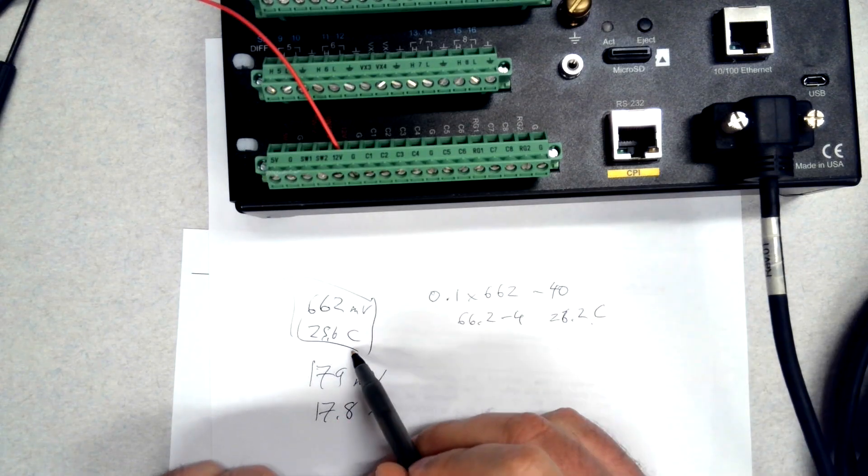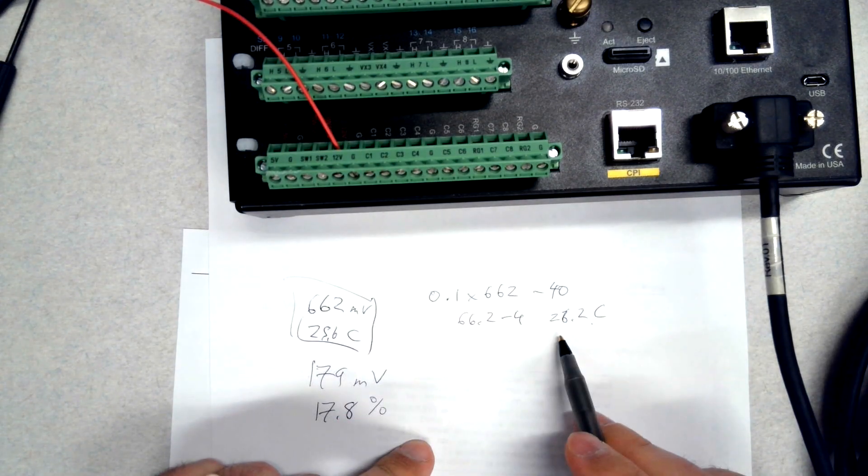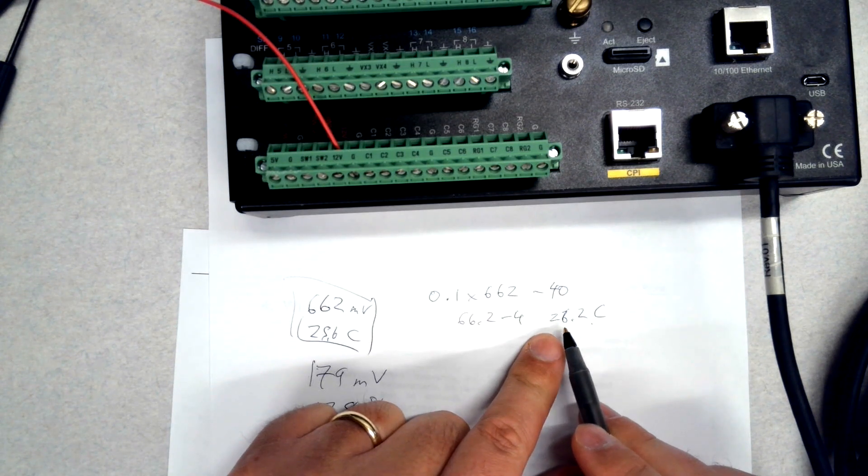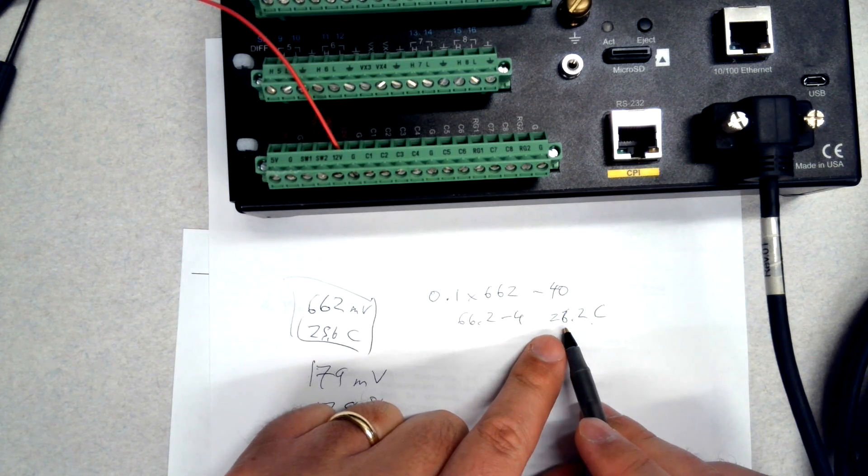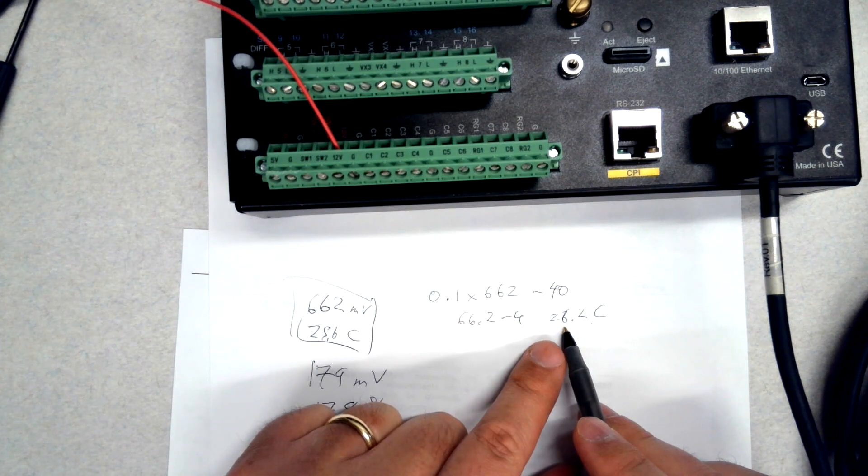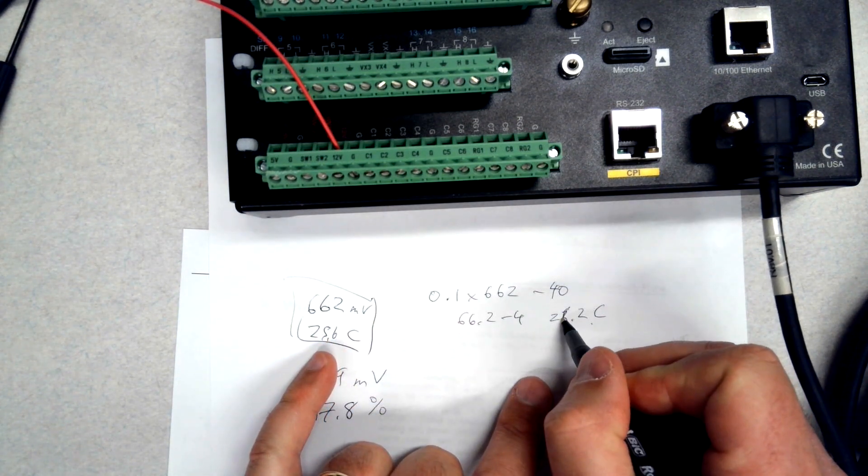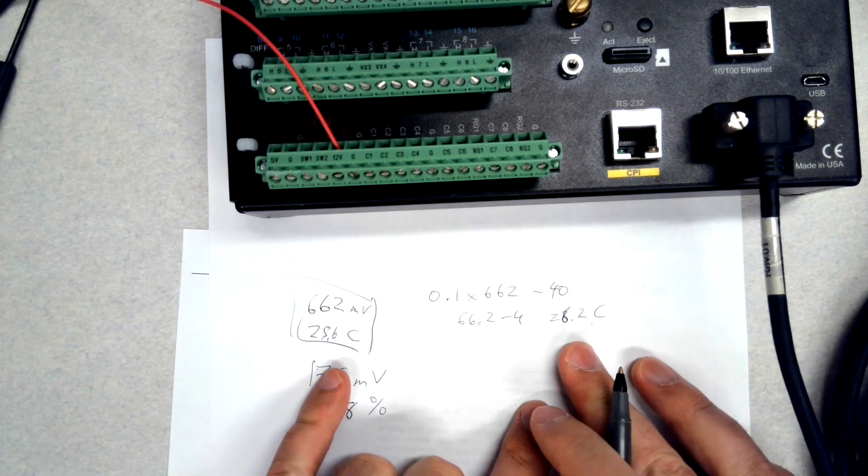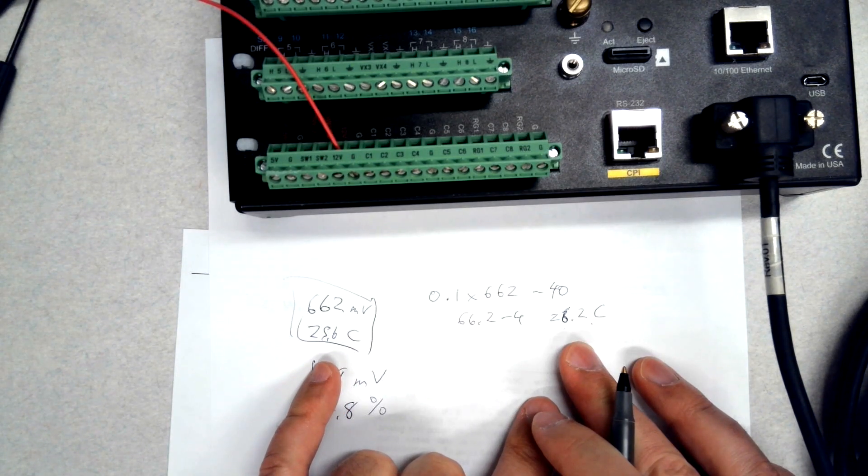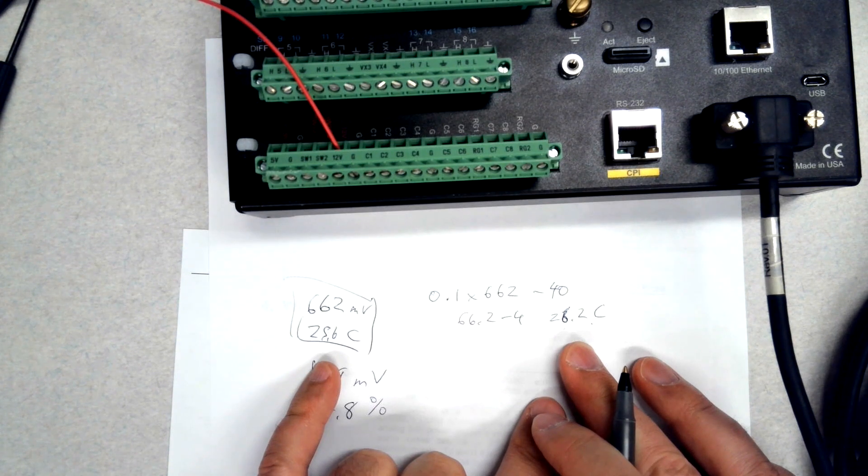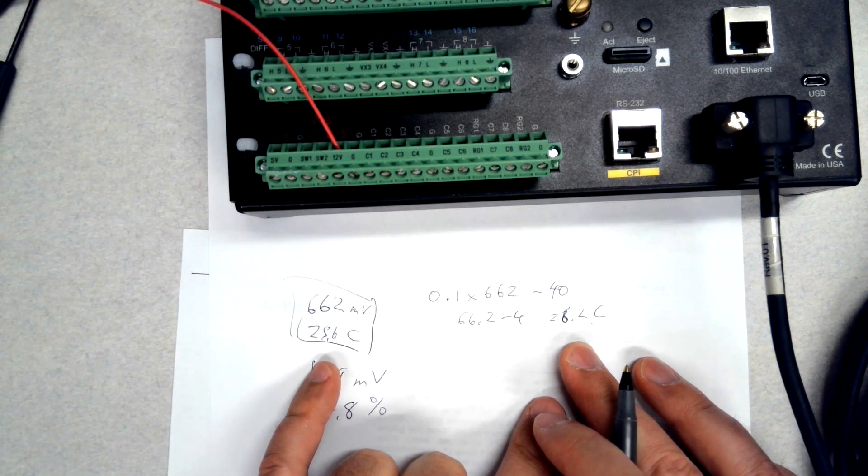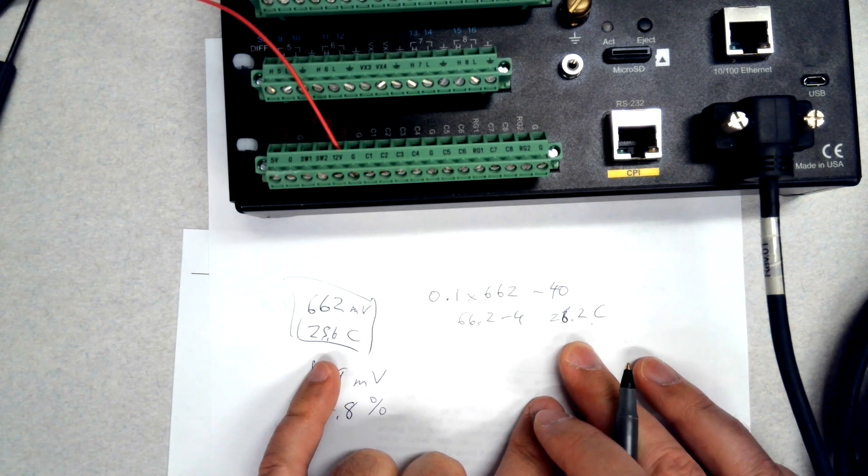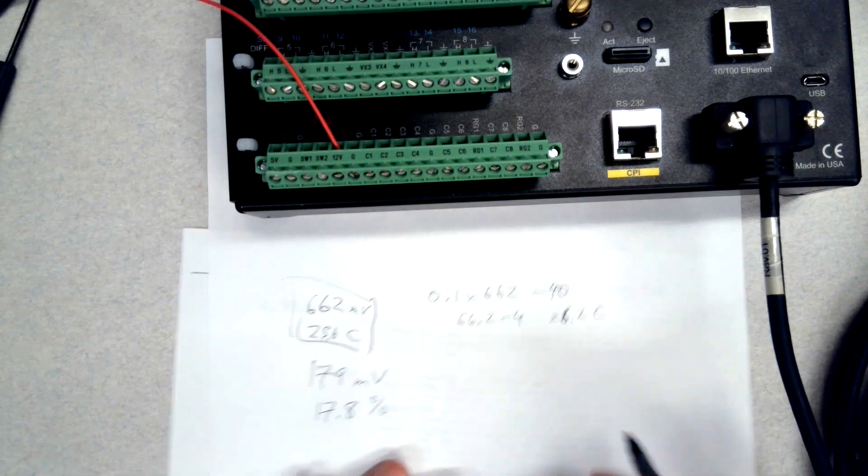It's important to note your meter may read close but be off a bit and still be indicating the data logger is working correctly. Because your data logger is a very high accuracy voltmeter, and unless your multimeter is an expensive model, the accuracy is going to be much lower than the data logger. So we're looking for close agreement, not exact numbers.